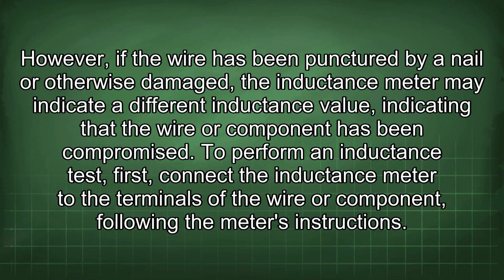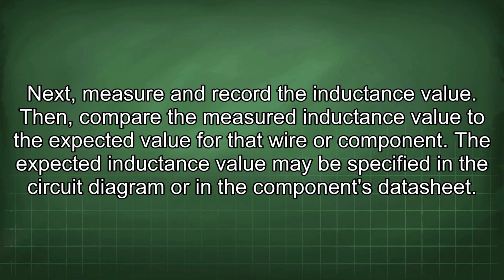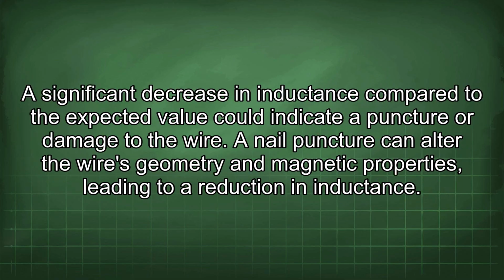To perform an inductance test, first connect the inductance meter to the terminals of the wire or component, following the meter's instructions. Next, measure and record the inductance value. Then, compare the measured inductance value to the expected value for that wire or component. The expected inductance value may be specified in the circuit diagram or in the component's datasheet. A significant decrease in inductance compared to the expected value could indicate a puncture or damage to the wire. A nail puncture can alter the wire's geometry and magnetic properties, leading to a reduction in inductance.